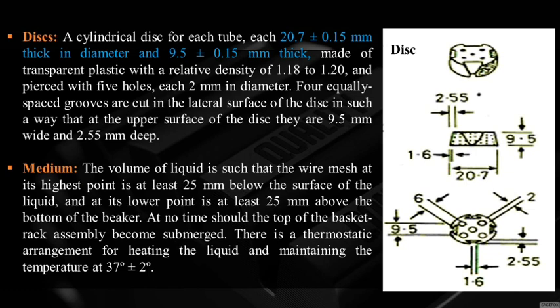At its lower point, the basket should be at least 25 mm above the bottom of the beaker. At no time should the top of the basket rack assembly become submerged. There is a thermostatic arrangement for heating the liquid and maintaining the temperature at 37 ± 2°C.